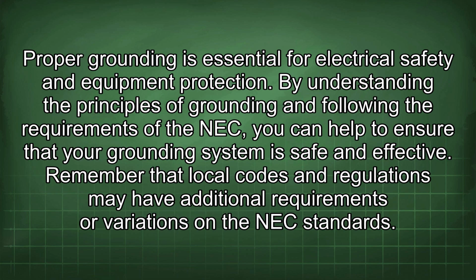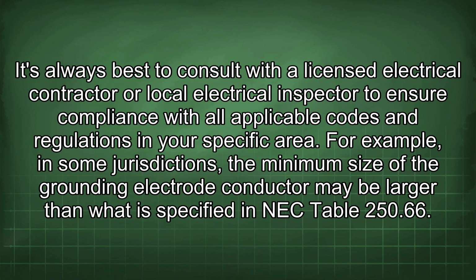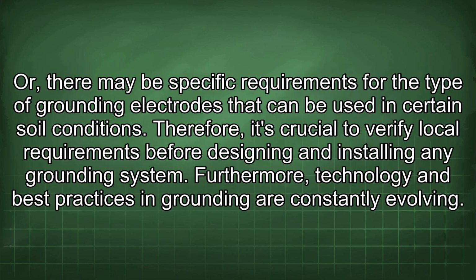Remember that local codes and regulations may have additional requirements or variations on the NEC standards. It's always best to consult with a licensed electrical contractor or local electrical inspector to ensure compliance with all applicable codes and regulations in your specific area. For example, in some jurisdictions, the minimum size of the grounding electrode conductor may be larger than what is specified in NEC Table 250.66. Or, there may be specific requirements for the type of grounding electrodes that can be used in certain soil conditions. Therefore, it's crucial to verify local requirements before designing and installing any grounding system.